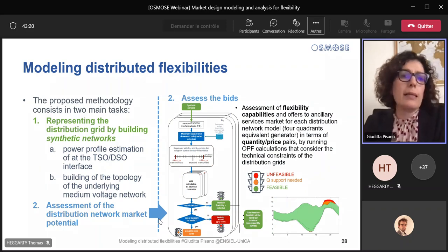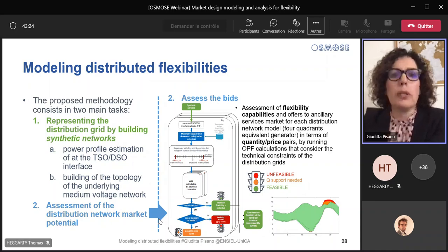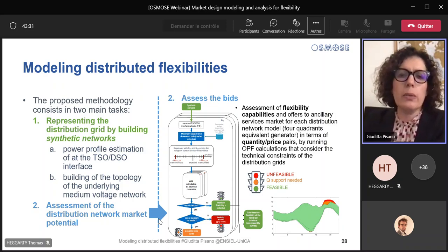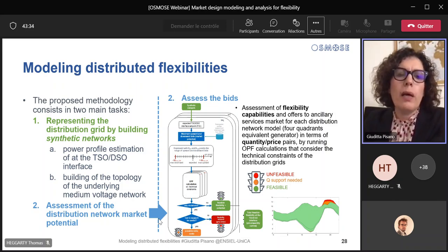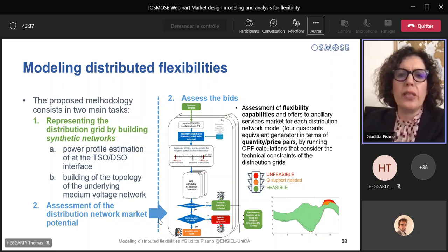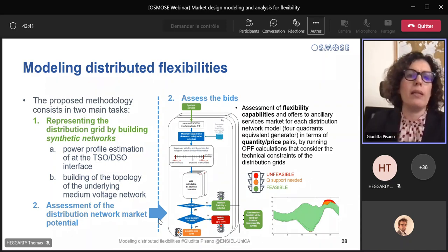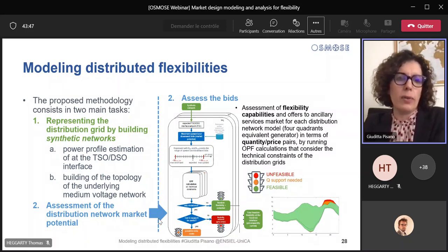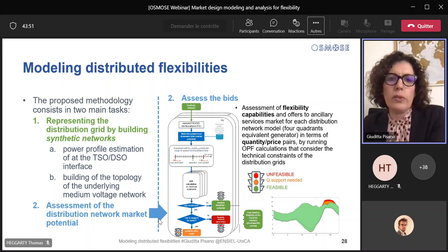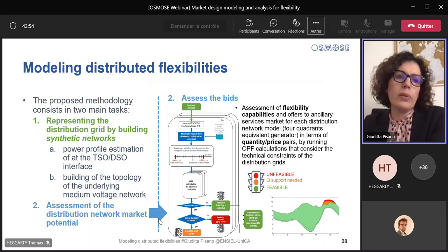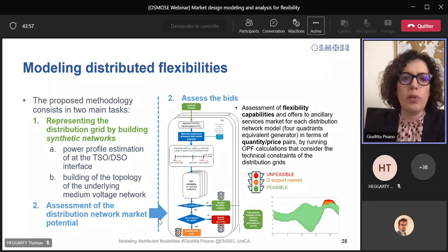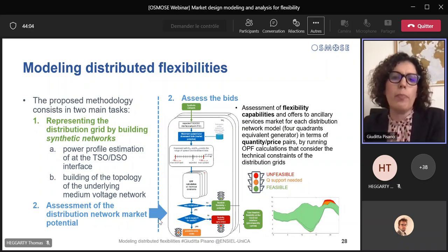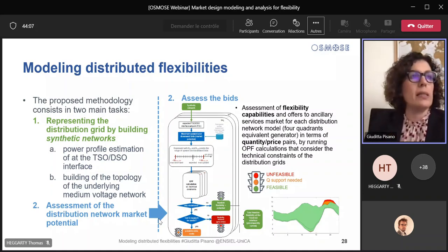The last task assesses the flexibility capabilities of each distribution network in terms of quantity and price pairs for each time interval, distinguishing between upwards and downward bids. Optimal power flow calculations are performed for identifying technical constraint violations. It may happen that no violations are found, and thus the feasible flexibility is the same as the potential. Otherwise, the violation can be solved by resorting to reactive power support, or in more critical conditions, the feasible flexibility is definitely reduced compared with the potential. The final results are the price-quantity curves and the profile of the feasible and unfeasible flexibilities.